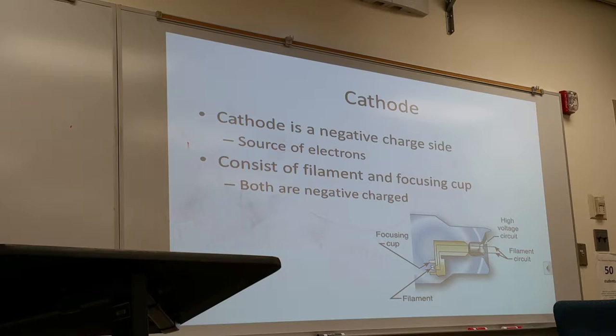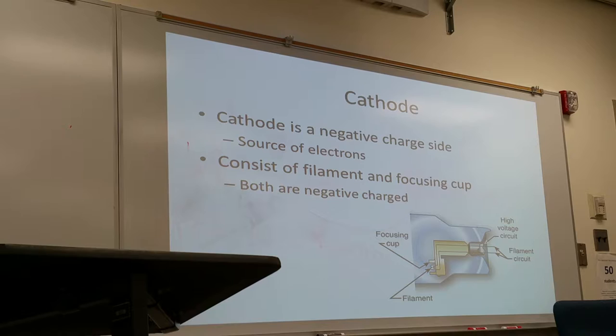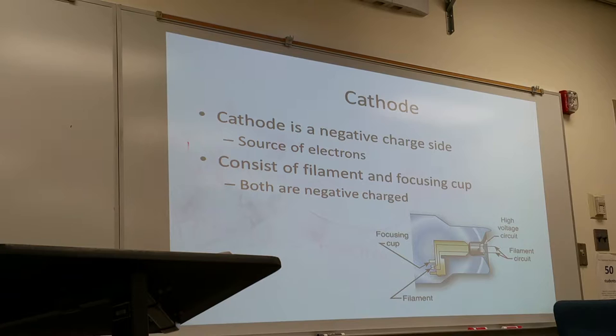The parts inside the envelope: the cathode side is the negative charge side of the x-ray tube. This is where we get the source of electrons to produce x-ray photons. The main components of the cathode side are the filament and the focusing cup. It is negatively charged, and this is where thermionic emission occurs from the filament.